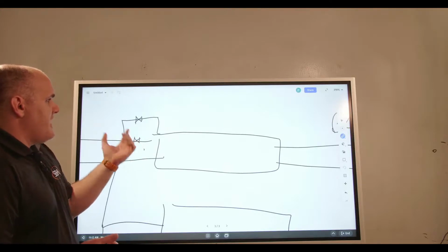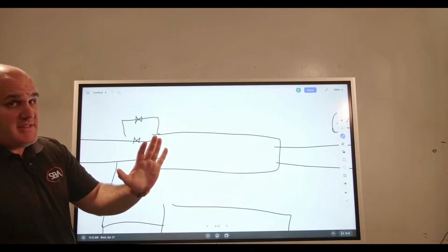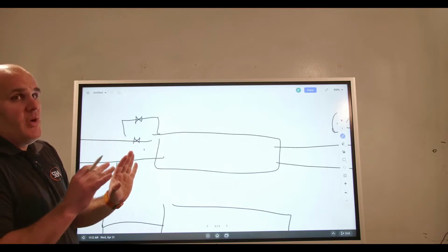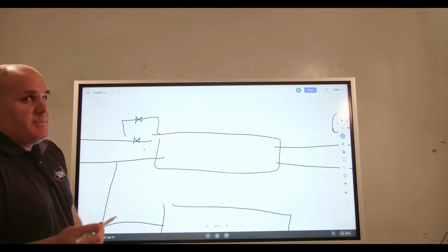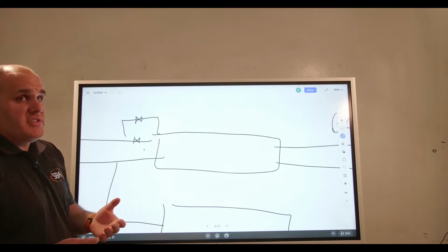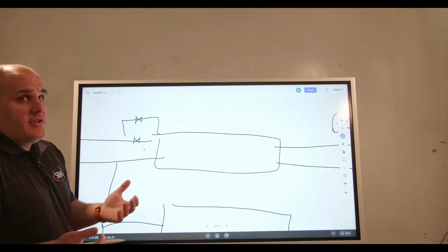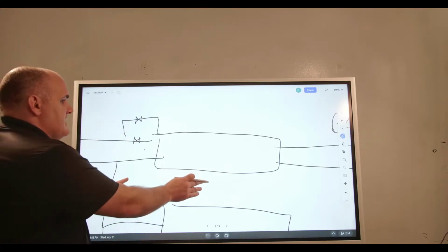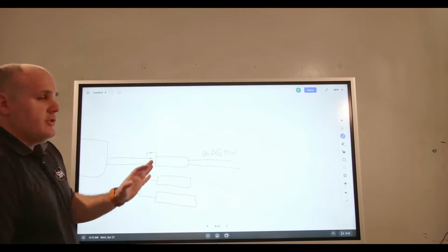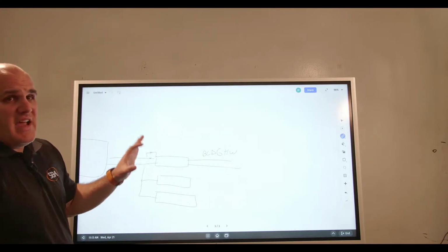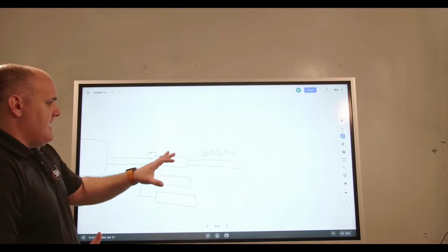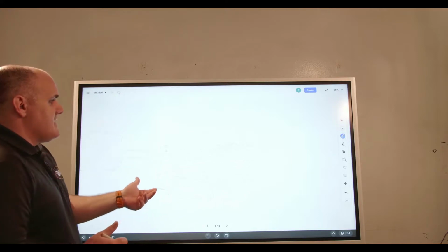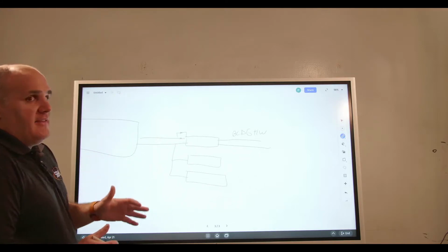So we'll close off that, we'll open up that 66%, and then if we're still not getting there, then we will start to open up the 1/3. How we'll typically do that is a PID loop with some scaled outputs to drive the 1/3, 2/3 outputs, and then we'll use some staging control as well. So that's typically what we're doing with this 1/3, 2/3 concept with steam, whether that's in an air handler or in the tubular heat exchanger as well. So that is the basics of hot water control.